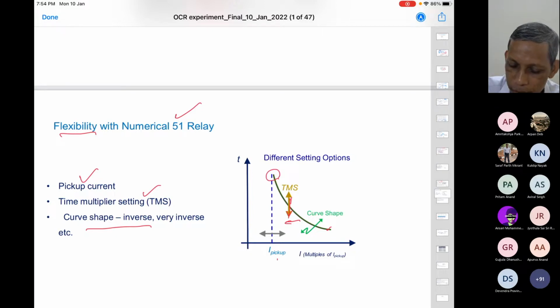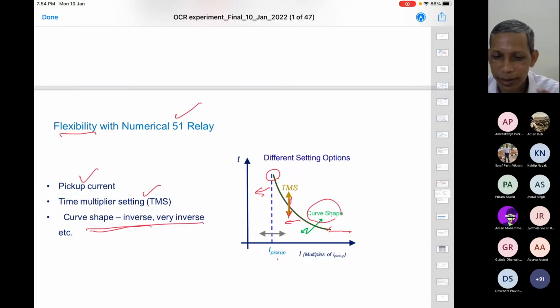Below pickup, that is, at less than pickup current, the relay does not trip. It means the time is infinity; it will not operate. And greater than pickup, it will trip. And how will it trip? For a very large current, the time is small, and then we have a definite time after that. If it is a medium level of current, the time is accordingly longer. Now, the shape of the curve, inverse, very inverse and so on, is governed by K, alpha, and L. So the three flexibilities in the characteristic of this IDMT are TMS flexibility, curve shape flexibility, and pickup flexibility. These are the three things.